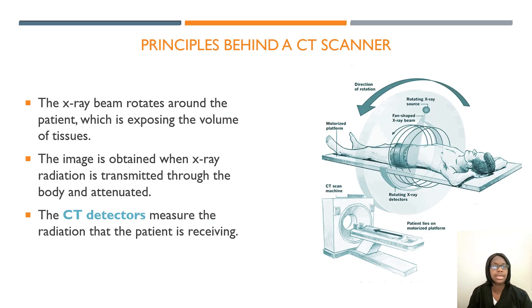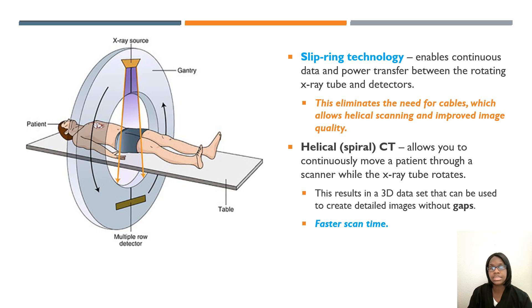The principles behind a CT scanner: the x-ray beam rotates around the patient, exposing a volume of tissues. The image is obtained when x-ray radiation is transmitted through the body and attenuated. CT detectors measure the radiation transmitted through the patient. Slip ring technology enables continuous data and power transfer between the rotating x-ray tube and the detectors, eliminating the need for cables, which allows helical scanning and improved image quality. Helical/spiral CT allows you to continuously move a patient through the scanner while the x-ray tube rotates, resulting in a 3D data set that can be used to create detailed images without gaps.